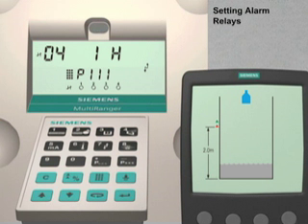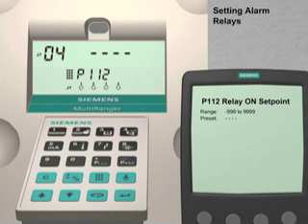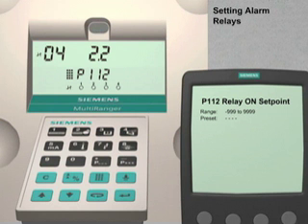The alarm set point values are stored in parameters 112 and 113. We will enter the on set point value first. Press the next display key. P dash dash dash is visible on the Multiranger display. Enter 112. The parameter 112 setting for relay number 4 is currently a null value as indicated by the four dashes in the parameter index field. Enter 2.2 followed by the enter key to set the on set point value to 2.2 meters.